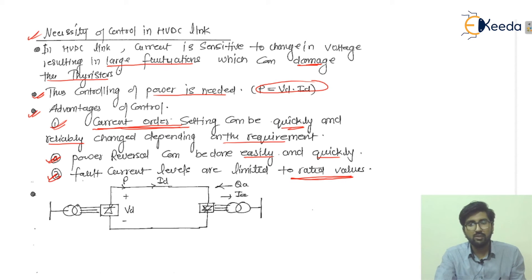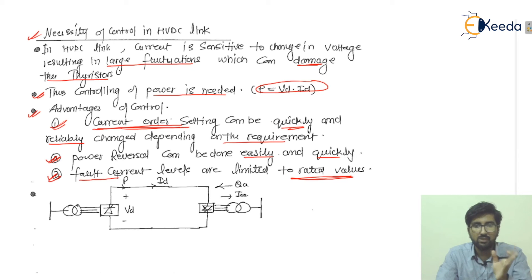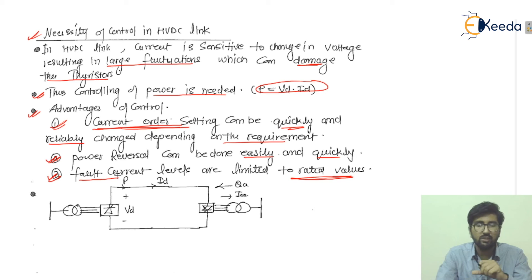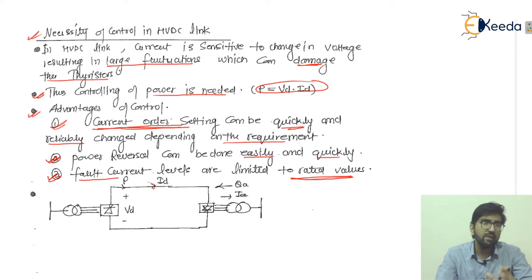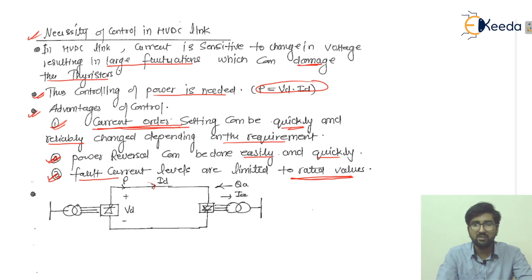Fault current levels are limited to rated values. If a fault occurs, the damage could propagate to other equipment. However, using control techniques on the rectifiers, inverters, and converters prevents the fault current from flowing and minimizes it to rated values. Because the resistance in HVDC links is low, high fault currents could otherwise damage equipment. This is a key benefit of using control schemes in HVDC systems.